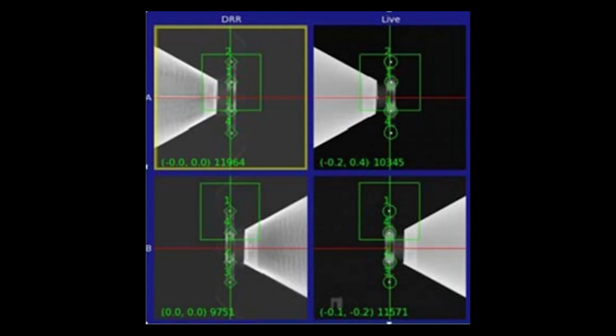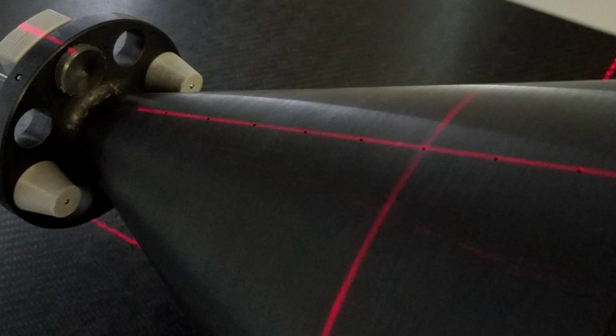These 4 fiducials are offset by 22.5 degrees, so orthogonal imaging systems like the Accuray CyberKnife can view all 4 puck BBs at the same time with each X-ray source and panel. There are 8 large holes located around the edge of the puck that are used to hold more fiducials. 2 of these holes are filled with what we call button or digit fiducials because they look like a small finger with a single BB in the center at the end.